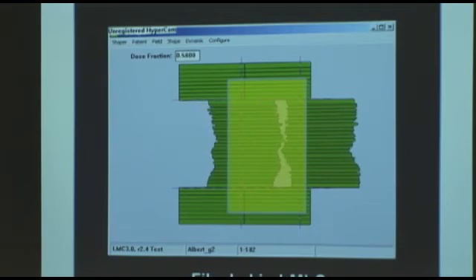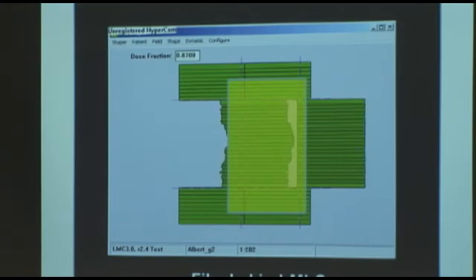So the parts of the MLC, the parts on that film that spend more time behind the leaf, are going to get less exposure than the parts which spend more time in the open aperture, right? So we're modulating the amount of photons that are able to come through and onto that film. So let's remove that and simulate the development of that film.